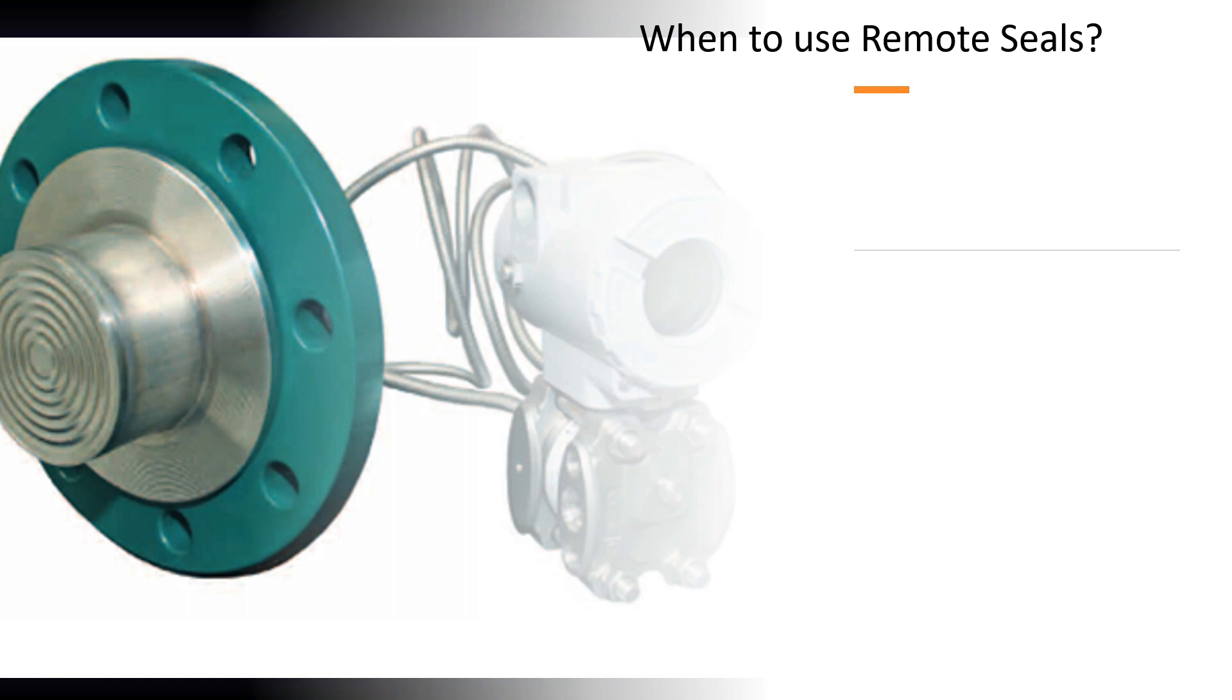Now comes when to use a remote seal. We're going to show here some situations. One of them is fluid temperature that's higher than the transmitter and sensor can support. If the transmitter, due to its sensor, due to its electronics, cannot support too high temperature, you must use a remote seal. That will keep the transmitter in a fresher place while the remote seal can stand to higher temperatures. Another situation is the transmitter will suffer frequent replacements due to being installed in an aggressive environment.